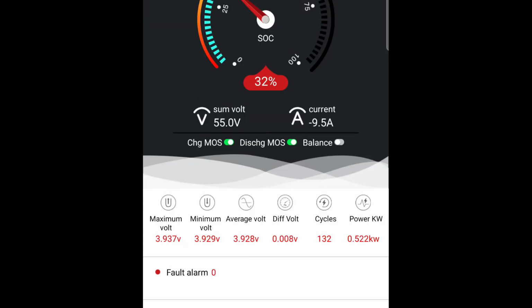Now notice the 3 LED indicators just below the SOC meter. One is the charge MOSFET. Green means it is now on, which means the battery is charging. The discharge MOSFET is also green, which means it is discharging also. And the balance LED is currently turned off, or it is not green, because the cells are already balanced, at 0.017 maximum difference. So therefore balancing is not being done at this moment. Once the cell difference voltage is over 0.02 volts, this balance LED will turn green and it will start the balancing.